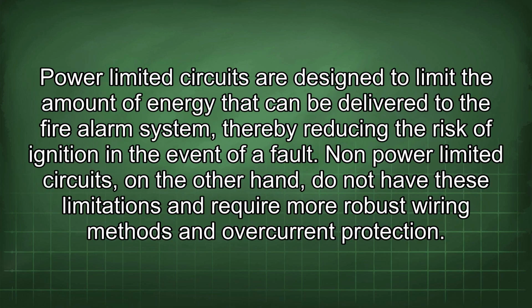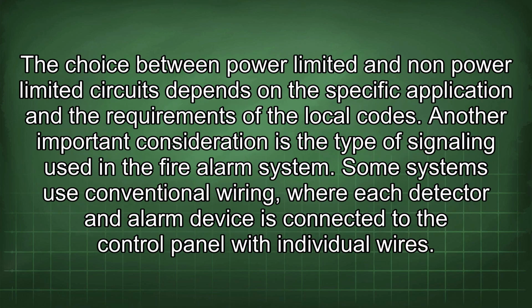Power-limited circuits are designed to limit the amount of energy that can be delivered to the fire alarm system, thereby reducing the risk of ignition in the event of a fault. Non-power-limited circuits, on the other hand, do not have these limitations and require more robust wiring methods and overcurrent protection. The choice between power-limited and non-power-limited circuits depends on the specific application and the requirements of the local codes.